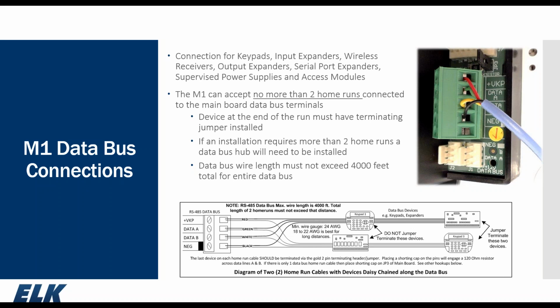We have built that resistor into our products already, so you don't have to worry about carrying another resistor with you. You engage the resistor by installing a black jumper in the appropriate location. For instance, on the M1 main board, the JP3 jumper here in the upper portion of the picture, when that jumper is across those 2 pins, that engages the 120 ohm resistor across data A and data B at the panel. For 2 home runs, like in our picture here at the bottom, where we daisy chain devices together, the last device on each home run would have that black jumper installed. That would engage the 120 ohm resistor. In this case, the panel, JP3, would not be terminated.